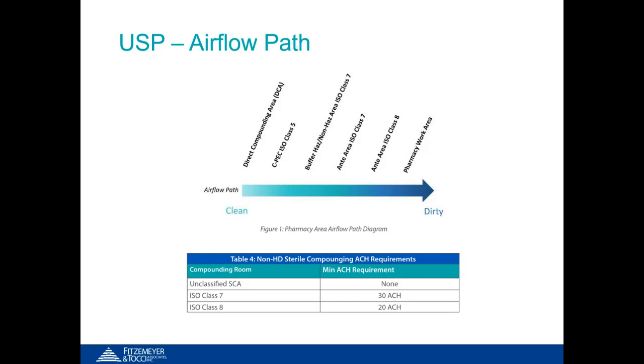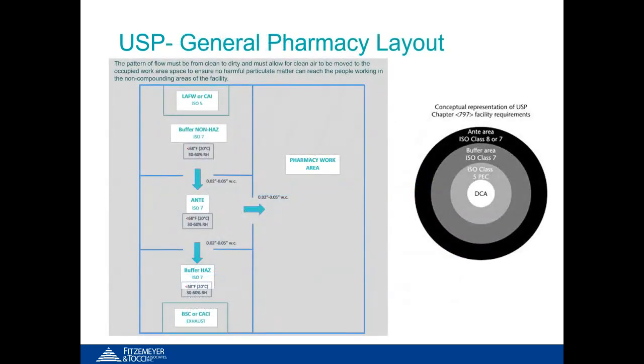The ISO Class 7 spaces require 30 air changes, and the ISO Class 8 spaces require 20 air changes. These ISO spaces are generally known as your clean rooms, where the unclassified SCAs are your general work areas. This is a typical general pharmacy layout that shows the airflow movement in accordance with the USP general chapters.